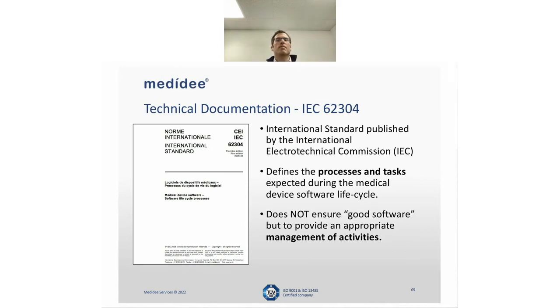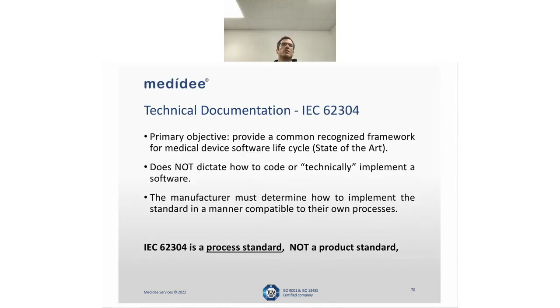In terms of standards, there are multiple standards, as you have understood. Where do you want to start? A very interesting one to look at in the medical software field is IEC 62304. It's not something very new. Unfortunately, the original version dates from 2006. The IEC has not been able to publish version 2.0; there was no consensus. Nonetheless, you will find the basic principles of good practices in software development. There is nothing really fancy here. It defines again this logic of how we structure requirements, the type of requirements, how we implement the design process, the fact that we have to do risk management, that we have to do maintenance, and so on and so forth. So you will actually use this standard to support the implementation of your design process with regard to software. It is still considered state of the art.